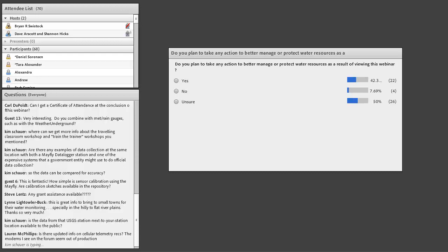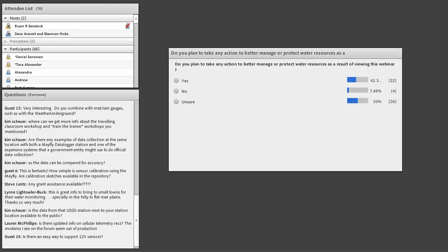There are other sensors that we have, like the turbidity, that is an analog sensor. So we're measuring an analog voltage, and then each specific sensor has a serial number, and I have a stack of 150 sheets of calibration curves for each specific probe. And if we move one probe from one Mayfly to another, we have to put that calibration information into the sketch. So there is a line or two in the Arduino sketch that gets written to the board that says we are using serial number 9972, and here's the calibration curve information for that. And so we do have to make sure that we track that, just like you would with any other data logger.